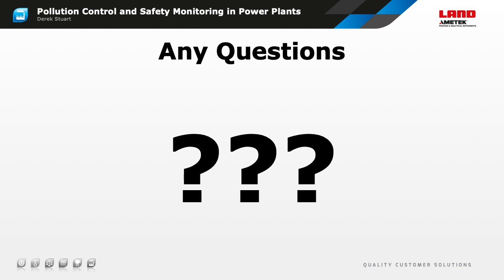Okay, another question here. How do I choose between an opacity monitor and PM-CEMS? In most cases, that's actually a choice that's already been made for you by the environmental regulations. If you're required to report opacity in percentage terms, then you require an opacity monitor, a transmissometer. If you're required to operate or to report your emissions in milligrams per cubic meter of dust, then you're looking at a PM-CEMS. There are some overlaps. An opacity monitor can certainly be calibrated to measure in milligrams per cubic meter, so you can actually get both measurements out of the same device.